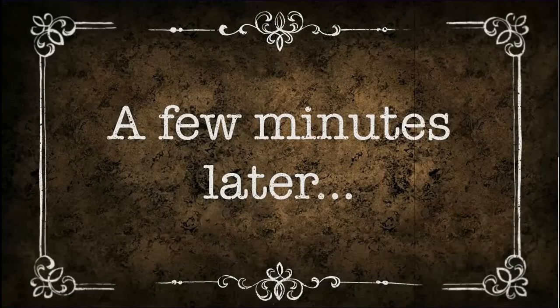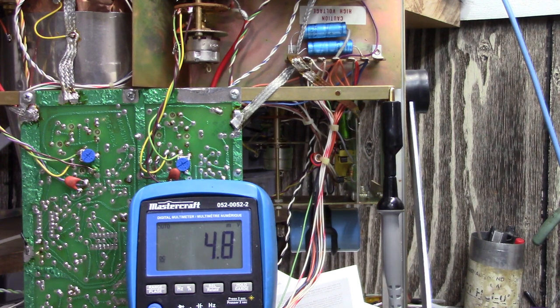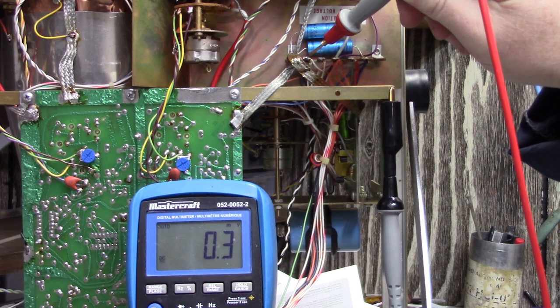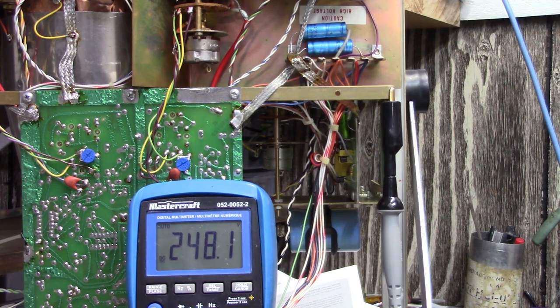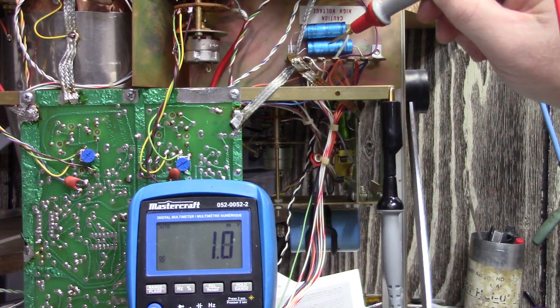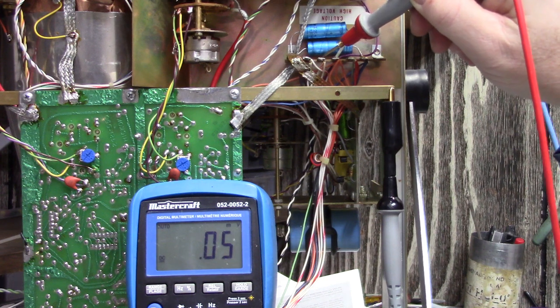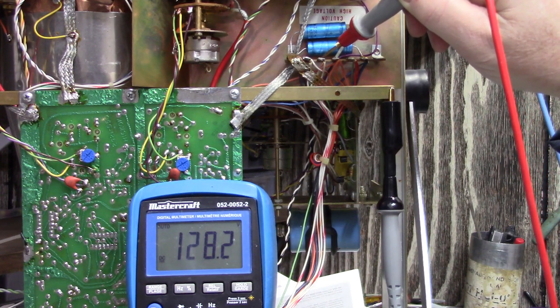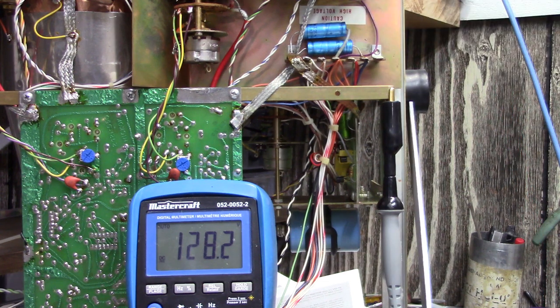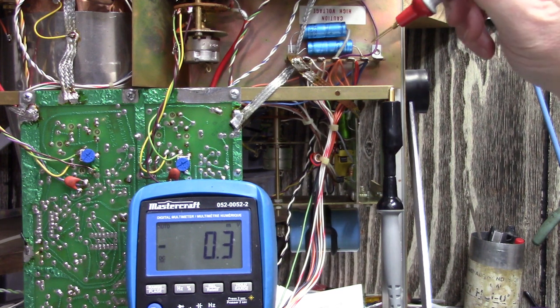A few minutes later. Okay, we'll let that sit enough now, and we'll test the voltages. So the first one is red and white. That should be 240 to 260. What are we reading? 248.2. Orange and white should be 120 to 128. 128.2. Little high, but not much. 128. Red should be 4 to 5.5 or something like that.